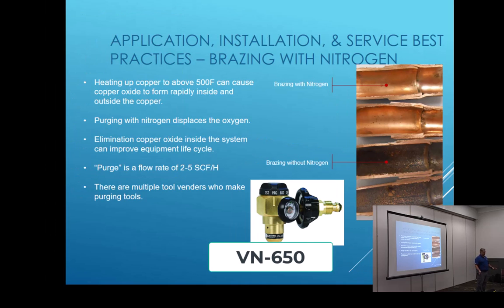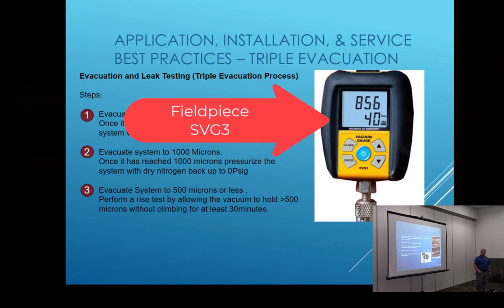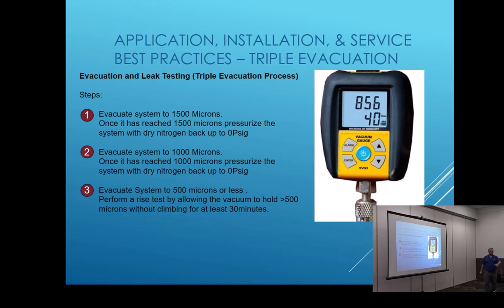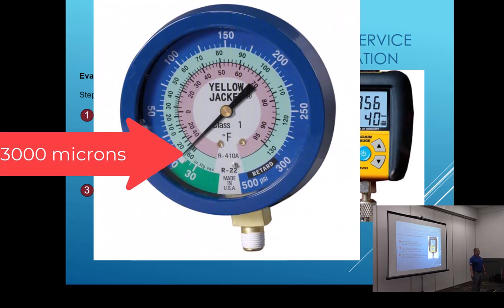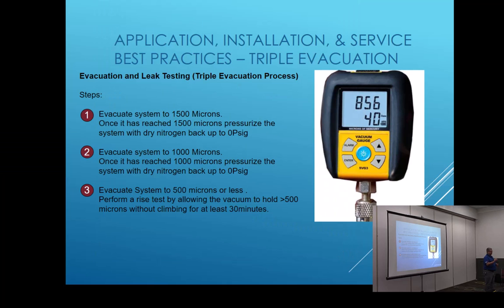Okay? Micron gauges. How many people have a micron gauge? Do we have digital gauges? Everybody got digital gauges. Does no one not have digital gauges? Okay? We need to start having digital tools. That's kind of why I got some of this up here. We're going to talk about tools in a little bit. But did everybody know that on our analog gauges, the needle width on an analog gauge is worth 3,000 microns? So just because it's down to 30 inches of vacuum, what's it at? 3,000, 5,000 microns? We don't know. Okay? With our digital stuff, we can get it down and we'll know what we're at. Okay? So it makes a difference. We've got to pull good vacuums on systems, guys.